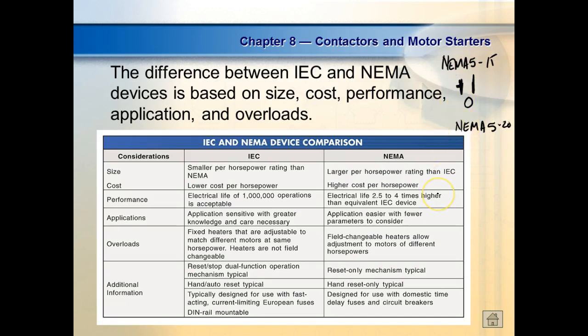So that means a device that's set to run on 20 amps will have the little L shape, right? So that means you couldn't plug it into a plug that's rated for 15 amps, but you could take a plug that's rated at 15 amps and plug it into a 20-amp receptacle. These are standards. Now you can look at NEMA standards.